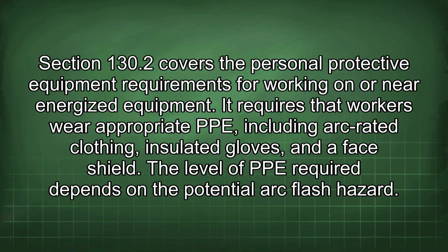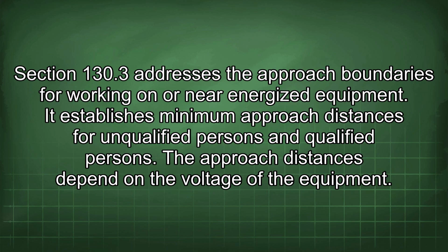Section 130.2 covers the personal protective equipment requirements for working on or near energized equipment. It requires that workers wear appropriate PPE, including arc-rated clothing, insulated gloves, and a face shield. The level of PPE required depends on the potential arc flash hazard. Section 130.3 addresses the approach boundaries for working on or near energized equipment. It establishes minimum approach distances for unqualified persons and qualified persons. The approach distances depend on the voltage of the equipment.